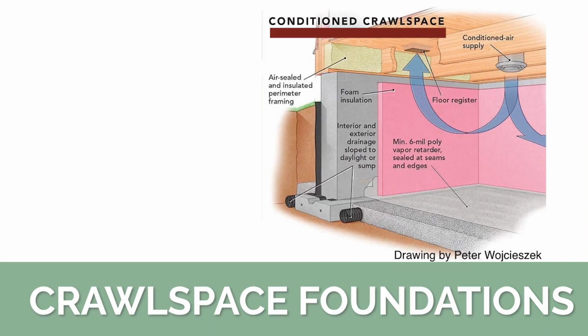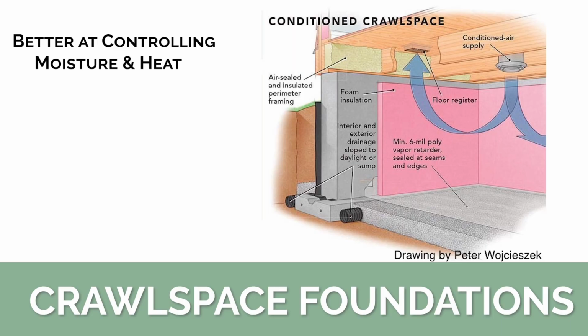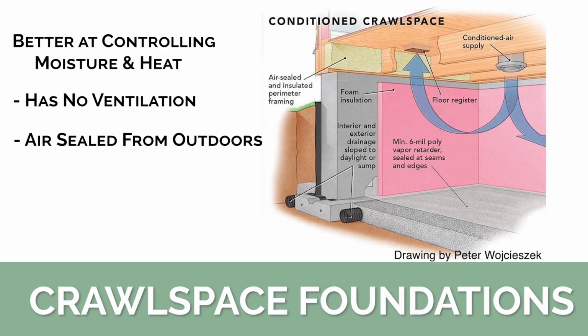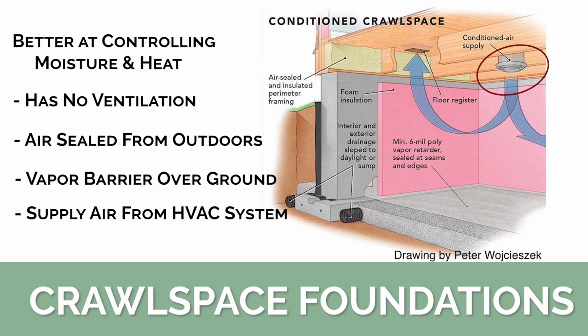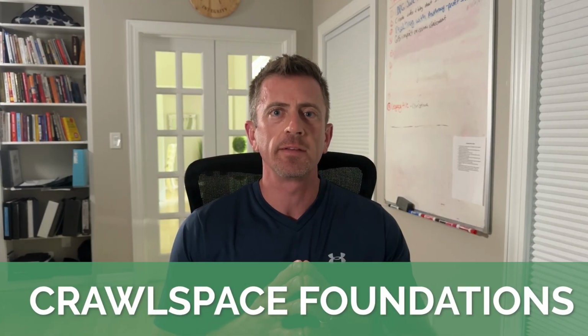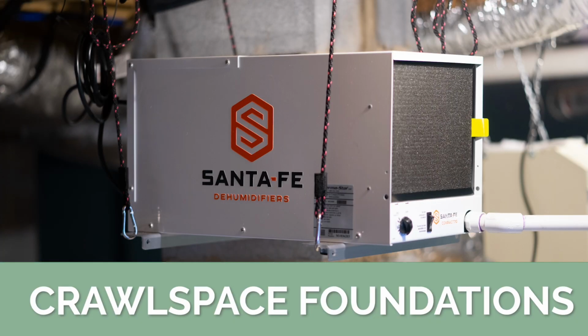Today, many new homes are built with conditioned crawl spaces that are much better at controlling moisture and heat. A conditioned crawl space is one that has no ventilation and is air sealed from the outdoors, has a proper vapor barrier installed over the ground that is sealed to the foundation walls that are insulated, and preferably insulated with closed cell spray foam or foam board insulation. They also typically have supply air coming from the heating and cooling system going directly into the crawl space to keep it roughly the same temperature as the rest of the house above. Sometimes installing a dedicated dehumidifier inside the crawl space is necessary to remove the moisture from there as well.